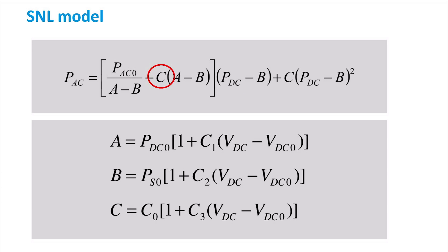we can find some coefficients already seen before, such as PDC0, which is the nominal DC input power, PS0, which is the night or self-consumption of the inverter, VDC, which is the PV array side voltage, and VDC0, which is the nominal DC voltage value. The last parameters are always provided by the manufacturers of the inverter.